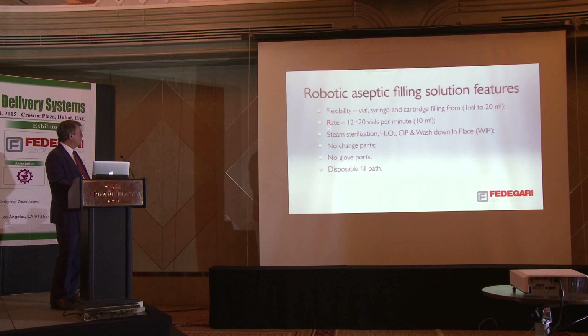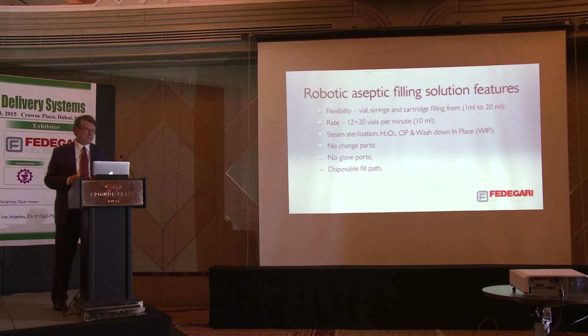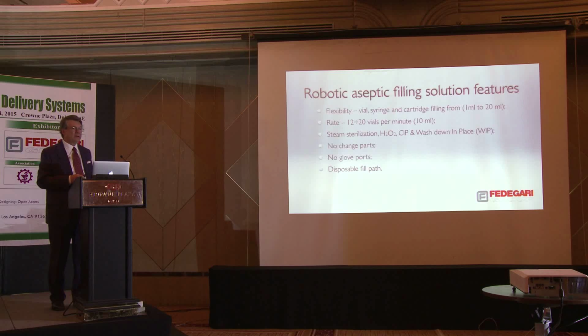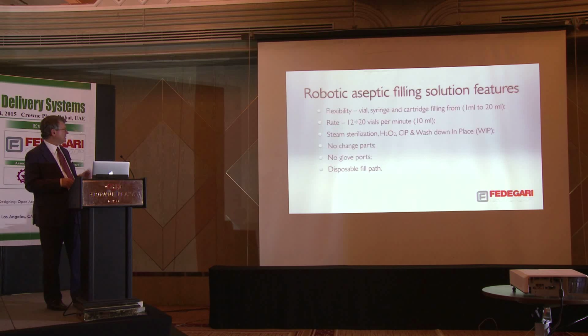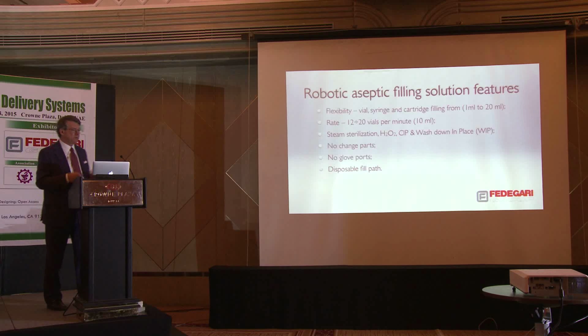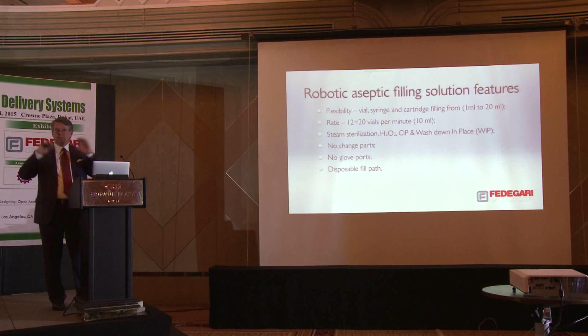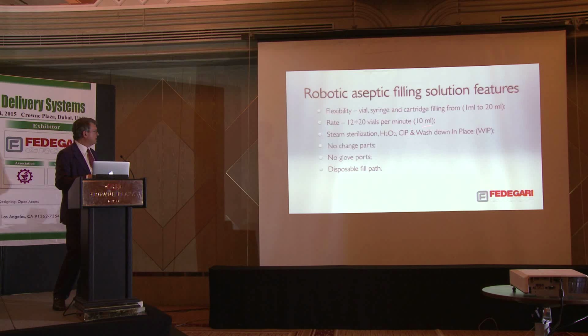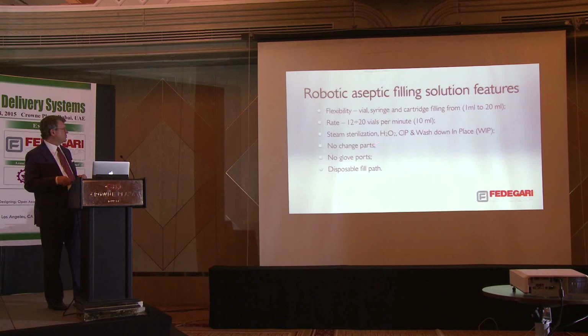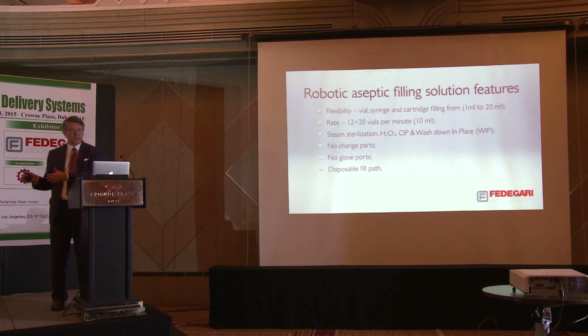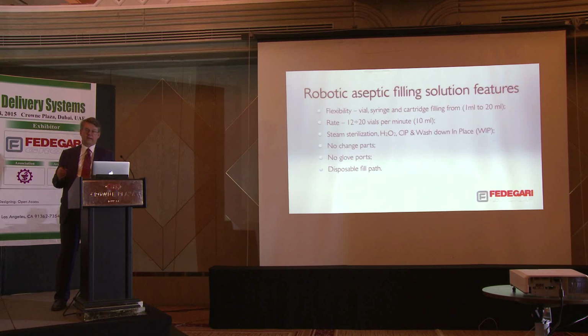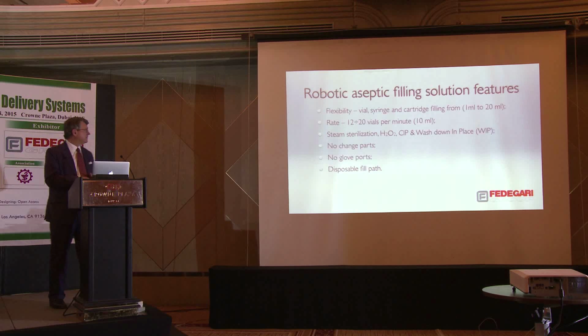Just to give you a quick idea, we can have an output rate of between 12 to 20 vials per minute, based on a 10 milliliter format. In our equipment, we have implemented steam sterilization for the primary container and hydrogen peroxide decontamination for the chamber of the isolator. So we can do clean in place, wash down in place. There are no change parts. Changing from one format to another is just a question of teaching the controller with the new software, size number 1, size number 2, size number 3.